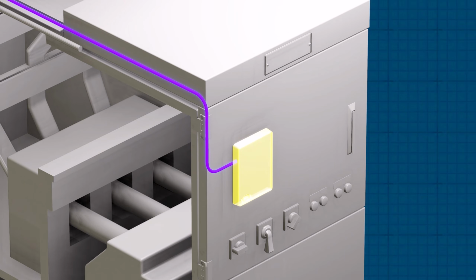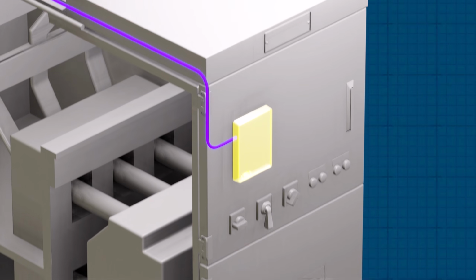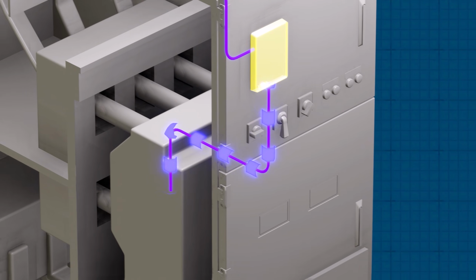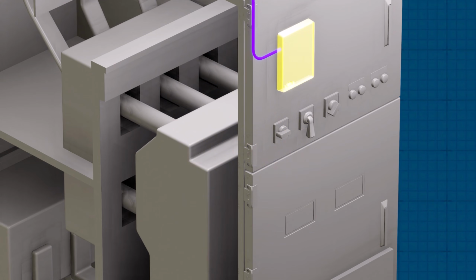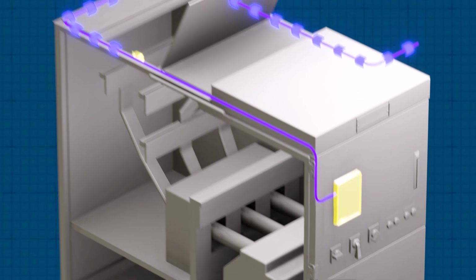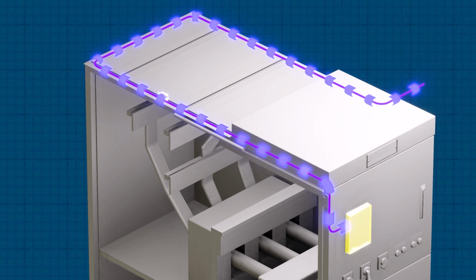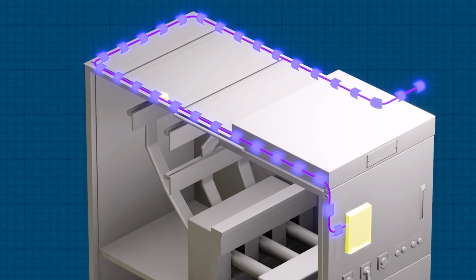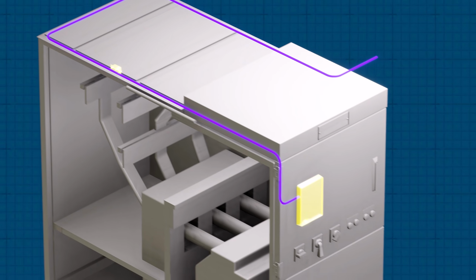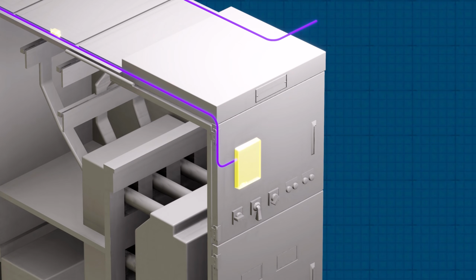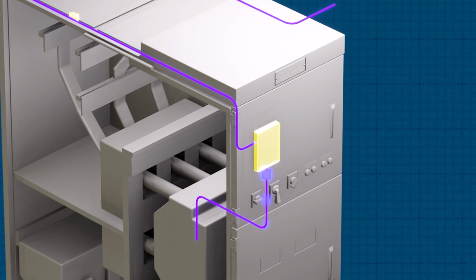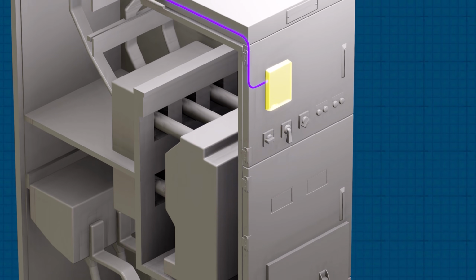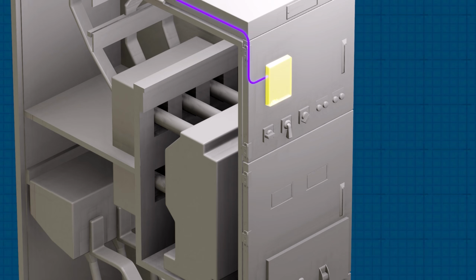When the protection relay detects a voltage collapse below 164 volts, it determines that the arc flaps must have opened and then sends a signal to the circuit breakers to trip the AC power. On the day of the incident, however, no such arc occurred. Instead, because the voltage in the DC system collapsed, the protection relay incorrectly determined that an arc had occurred and the switch had opened. It then sent a signal to the circuit breakers to trip the AC supply.